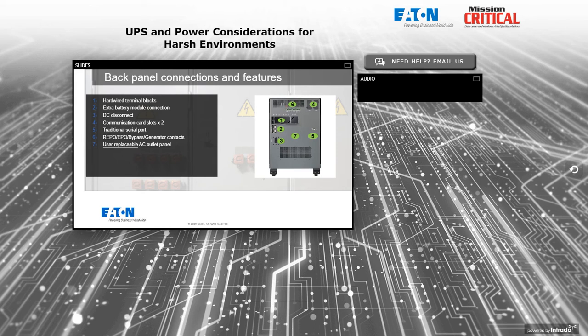Back panel features are access for connections, terminal blocks. If I'm going to hardwire it, obviously I may have a cord and plug and wouldn't need the terminal blocks. The ability to have an extra battery cabinet or battery system connected, and to be connected in such a way that it doesn't cause a safety hazard. These are the kind of things that UL covers when the UPS system is listed for UL 1778 or other applications. If you're going to have a plug-in termination for extra batteries, it cannot be the kind where you can inadvertently poke your finger into, for example.